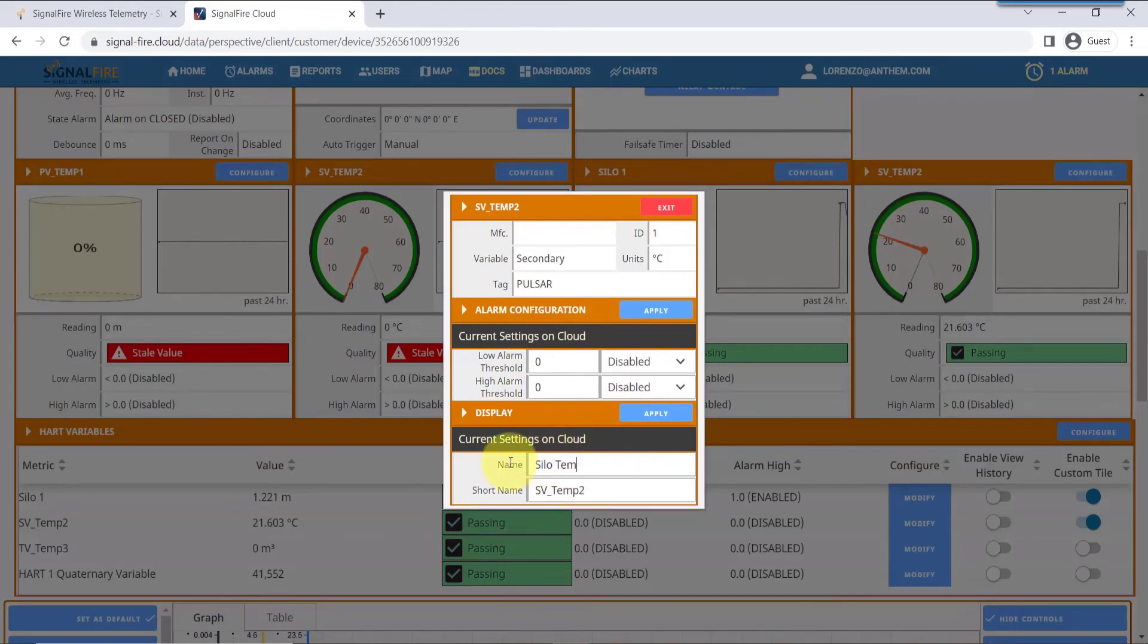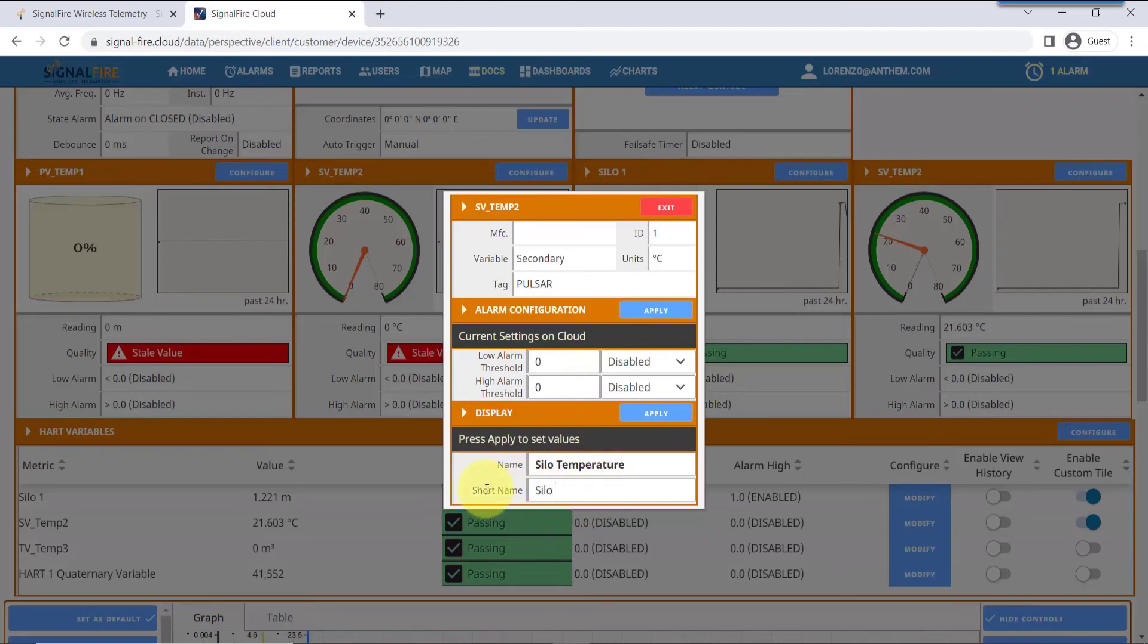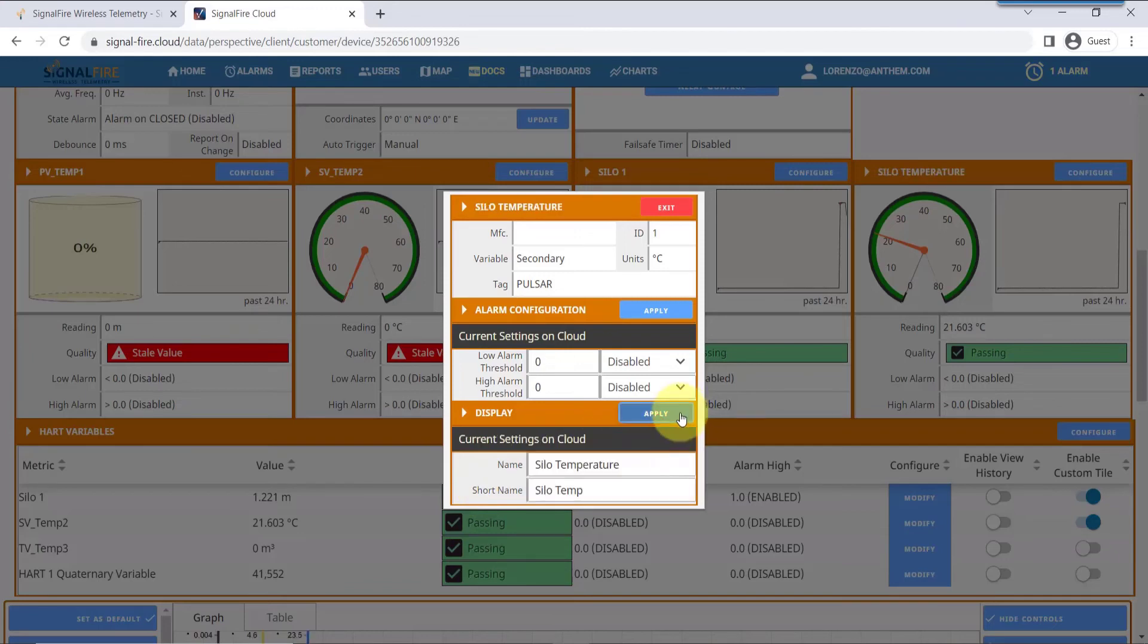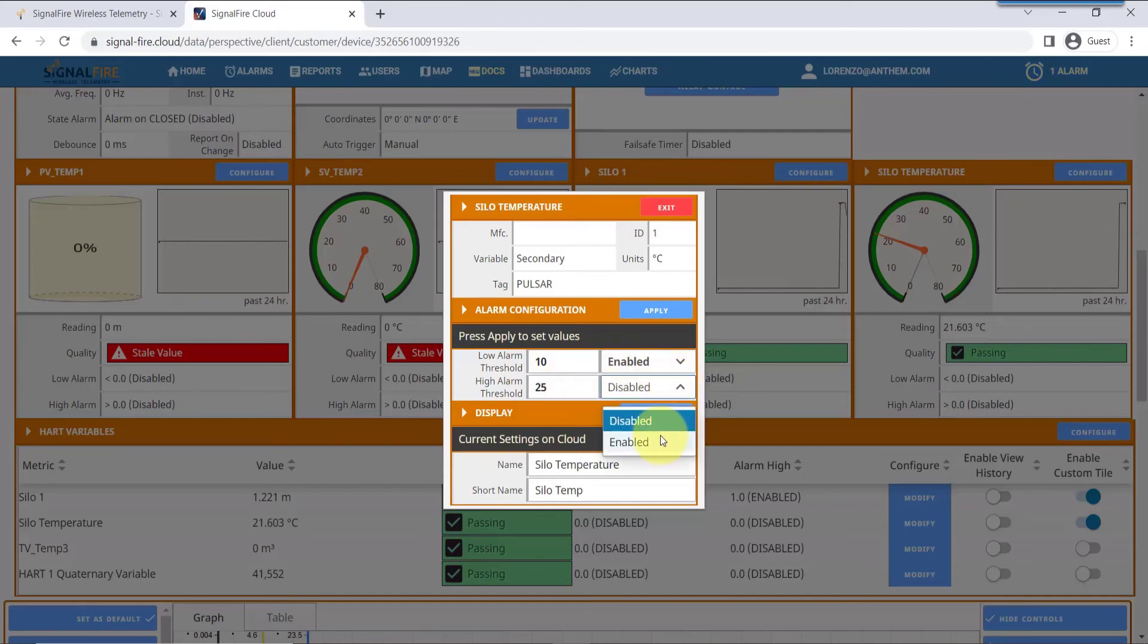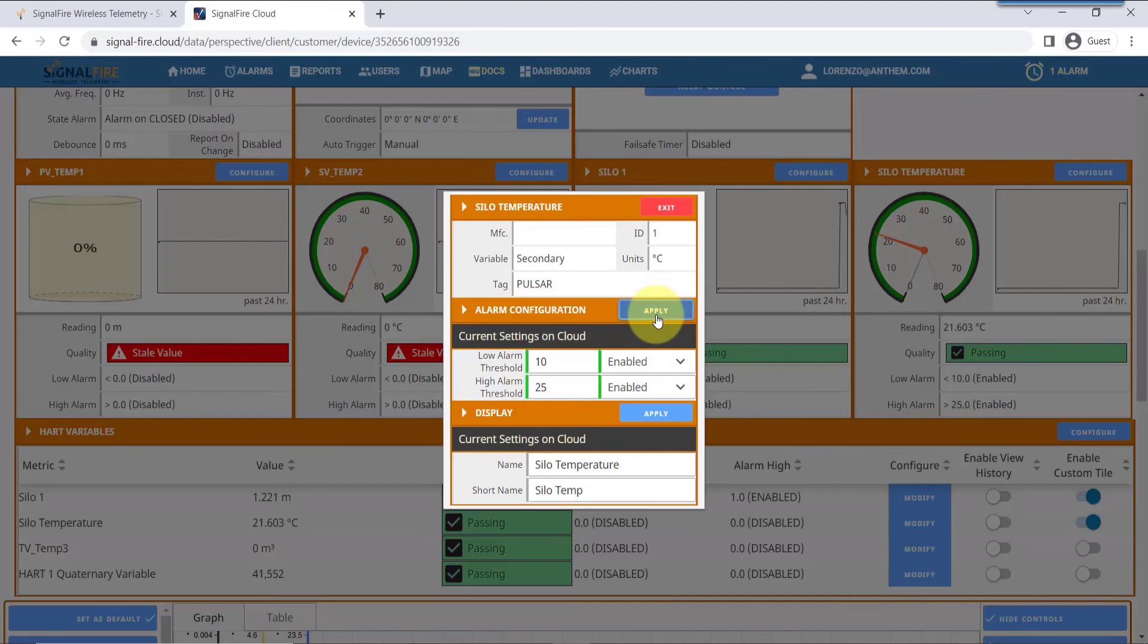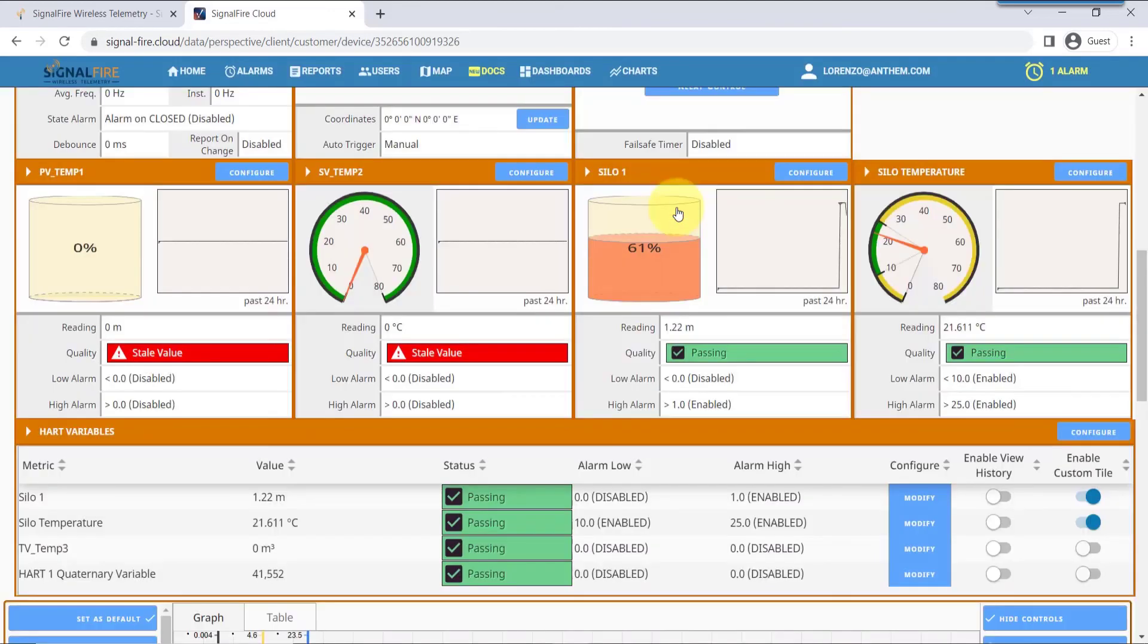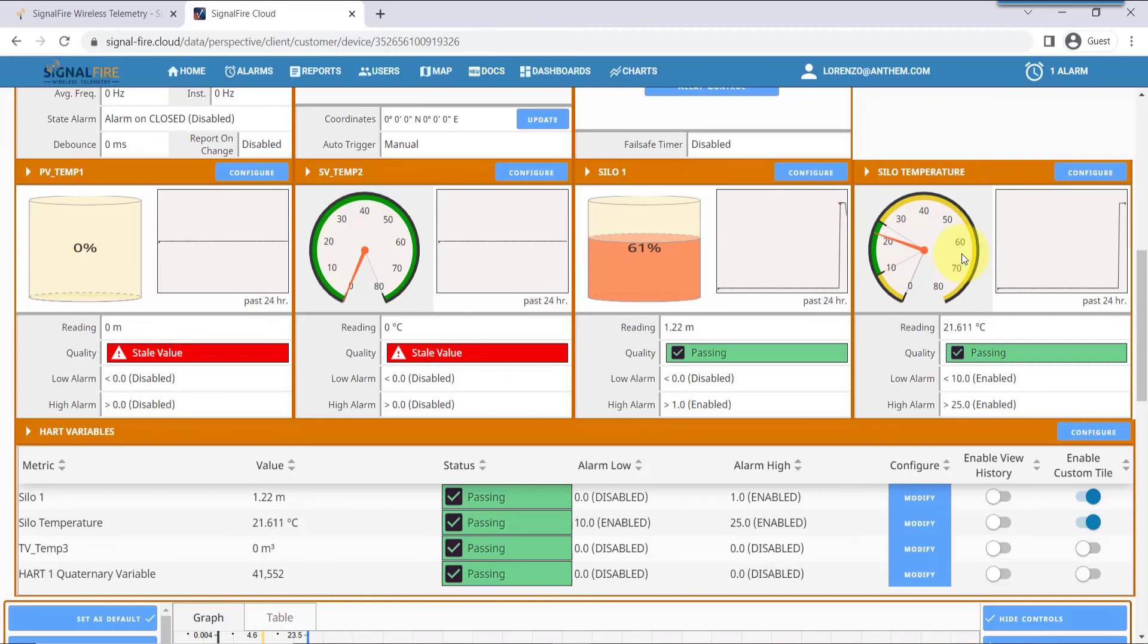I'm going to use Silo Temperature. I think that's more meaningful. Hit apply. Wait for the change to take place when it turns green. And then here, I'd like to have an alarm when the temperature is less than 10 degrees or more than 25 degrees. This will also affect how the display is shown on the dial indicator. That way you can see the needle being in the green zone, or the yellow zone, which will be the alarm zone that you just set.